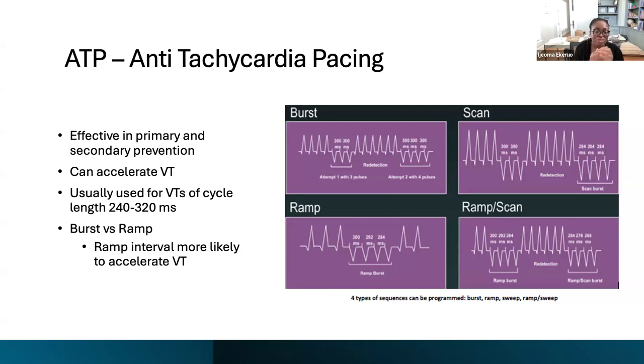So the ramp actually does it the opposite way, where within the actual cycle, it will go down and decrement in the cycle length. For instance, in the burst, it went 300 milliseconds each time. In ramp, it'll go 300, then 292, then 284, and continue to go down for the number of pulses you want to give.